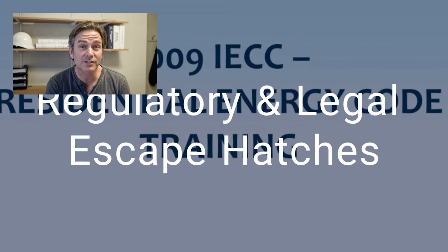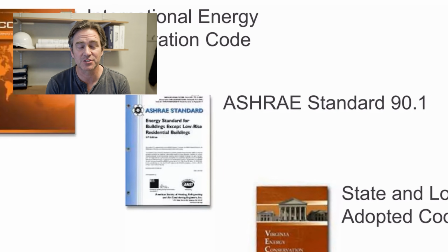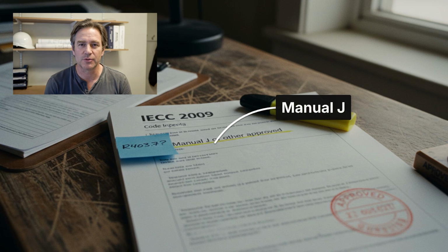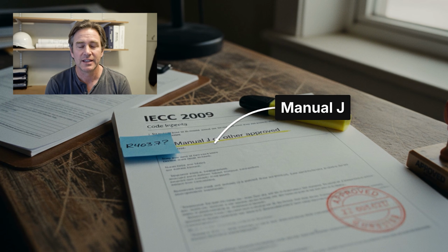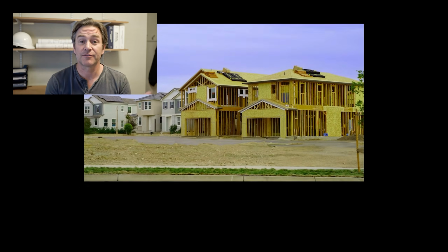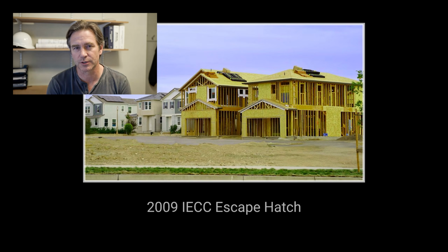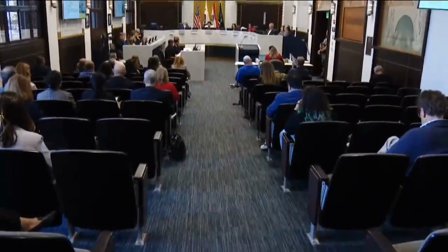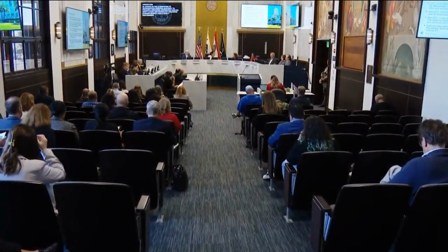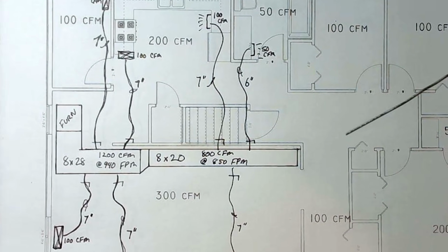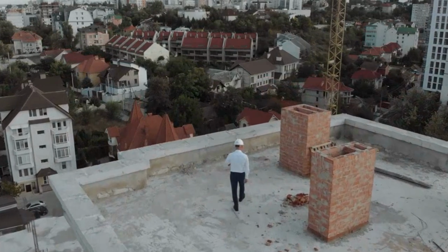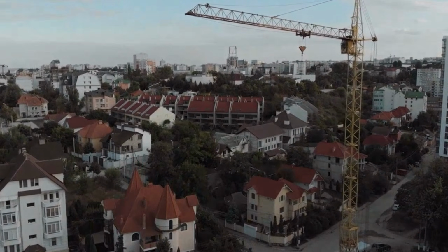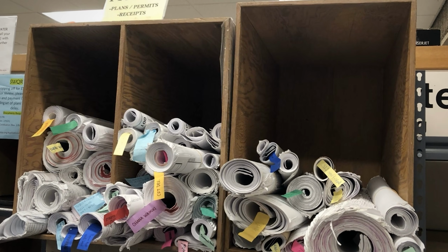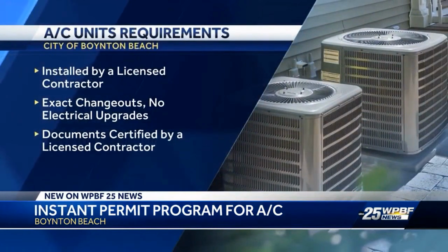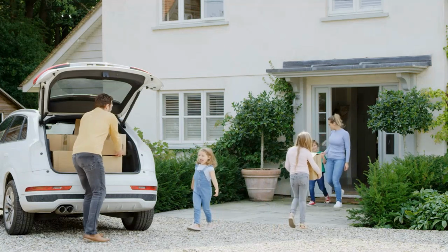The 2009 International Energy Conservation Code was supposed to require Manual J calculations for all new residential HVAC installations. The code language said Manual J, or other approved heating and cooling calculation methodologies. That phrase became the legal escape hatch that production builders drove through for 15 years. Their lobbyists and code compliance teams argued successfully that their rule of thumb method was an approved equivalent. City inspectors, overwhelmed and conducting 15-minute walkthroughs on complex structures, were in no position to challenge that argument. The undersized system got its permit. The drywall went up. The homeowner moved in.